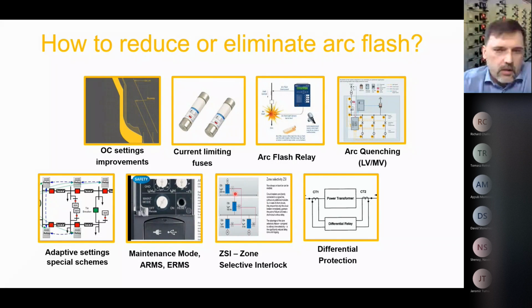Zone selective interlock. This is a nice feature to have. The name is for the low voltage systems, which is generally protection based on communication between the breakers. Very interesting topic. Actually, it's very often included in the modern digital relay, digital trip units of the low voltage breakers. And the same thing you might have in the medium voltage relays, which is called protective relay blocking scheme. More or less this way.